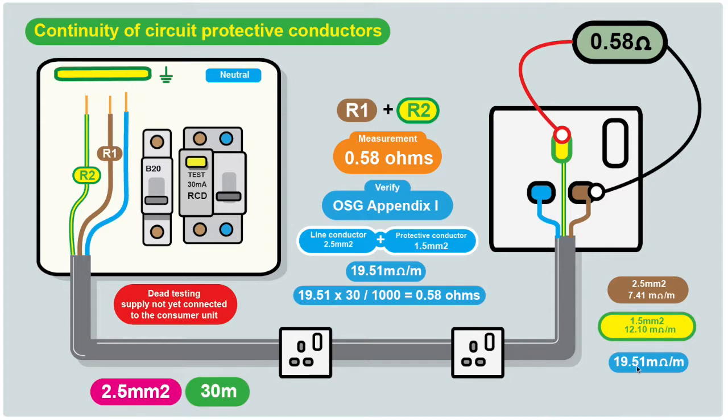The protective conductor has a smaller cross-sectional area of 1.5 millimeter squared, hence the resistance is slightly higher at 12.1 milliohms per meter. The table also does a combined measurement of resistance for the line conductor and the protective conductor. This is quite handy when you're measuring or calculating your twin in earth cable. You just use that one reading, 19.51 milliohms per meter.